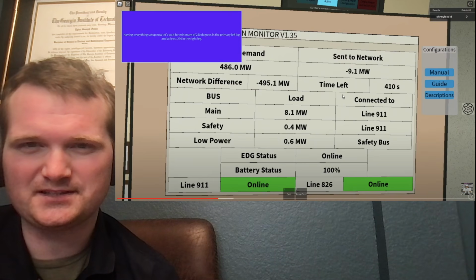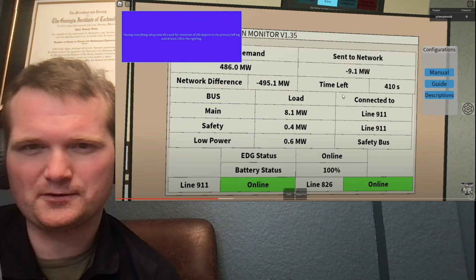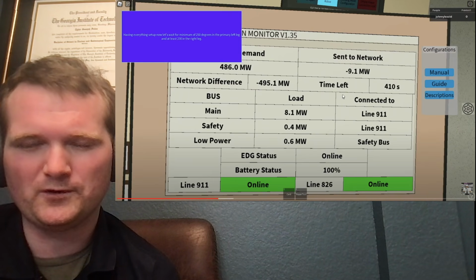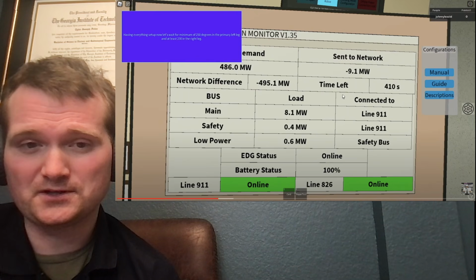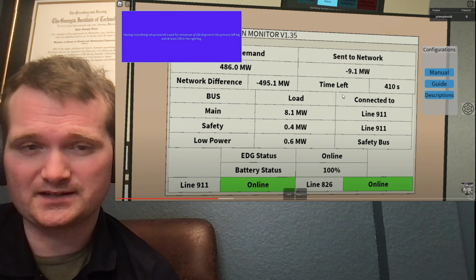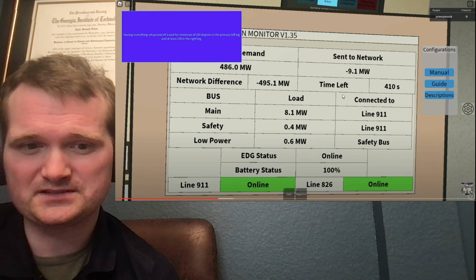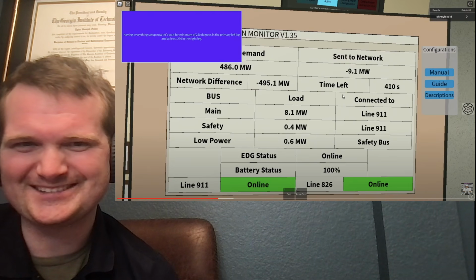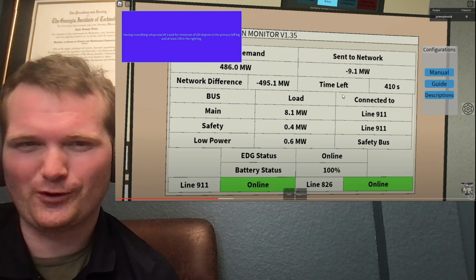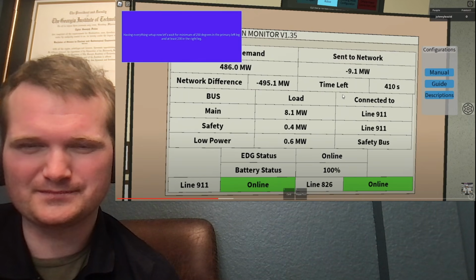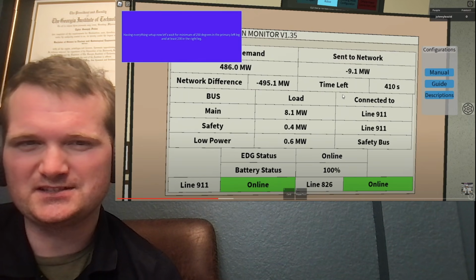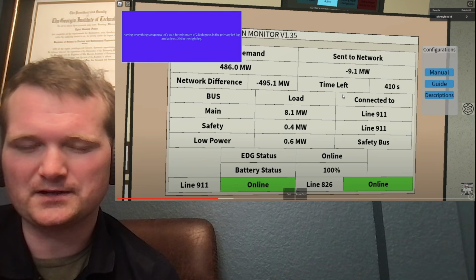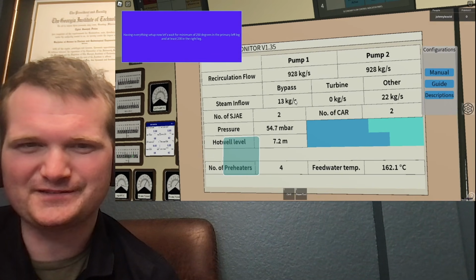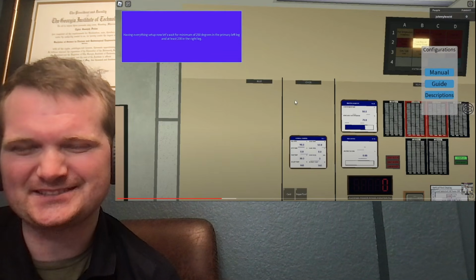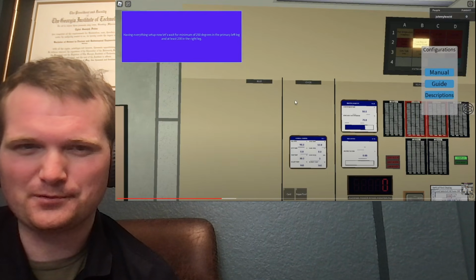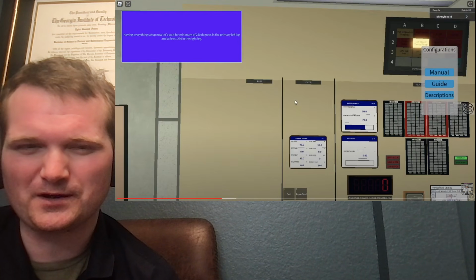And I can see sent to network minus 9.1 megawatts. So that means we're taking 9.1 megawatts from the grid, which makes sense. Turning on reactor coolant pumps, condensate pumps, feed water pumps, and possibly that superheater they installed, but that probably uses magic. 9.1 megawatts is not a surprising number. Line 911. And EDG stands for emergency diesel generator. Rods off, boron off. It's really boric acid that you would inject into the reactor. And boric acid, think liquid control rods.